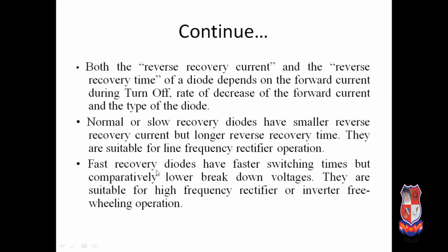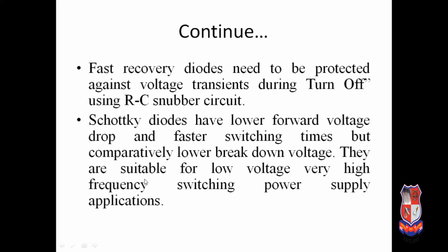Now the fast recovery diodes have faster switching time but comparatively lower breakdown voltage, and they are suitable for high frequency rectifiers. So according to the rating, you can decide for which application you will use the normal or slow recovery diodes and which application you will use the fast recovery diode. Please keep in mind that for the lower frequency line frequency rectifiers, you use normal and slow recovery diodes, and for high frequency rectifiers, inverters and freewheeling operations, you use fast recovery diodes.